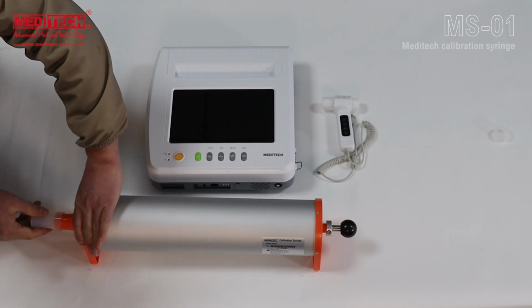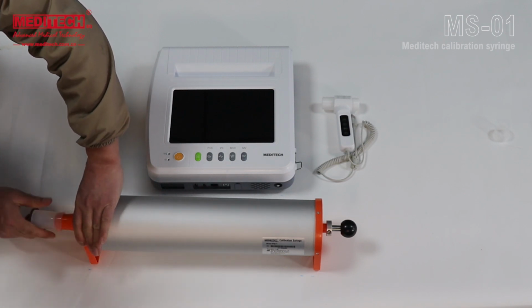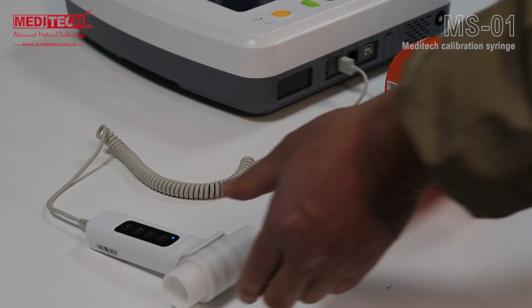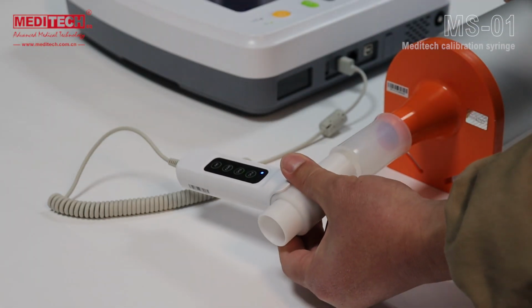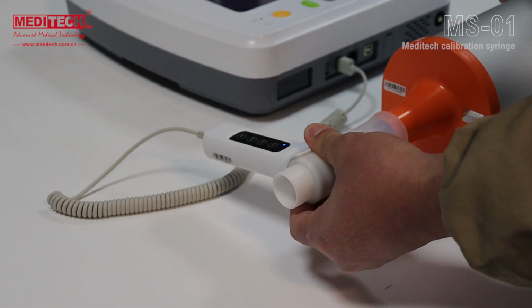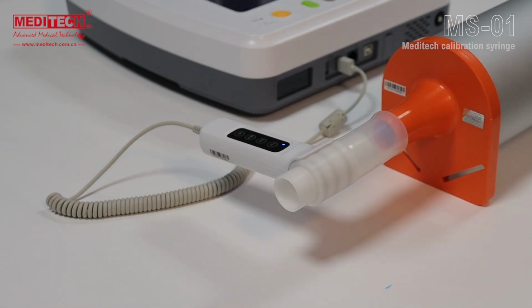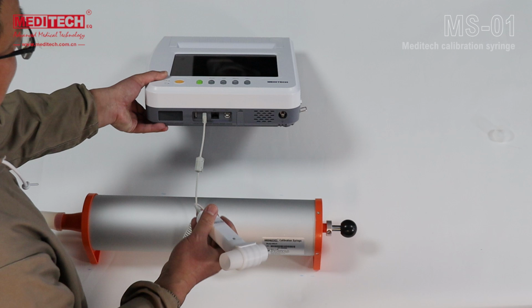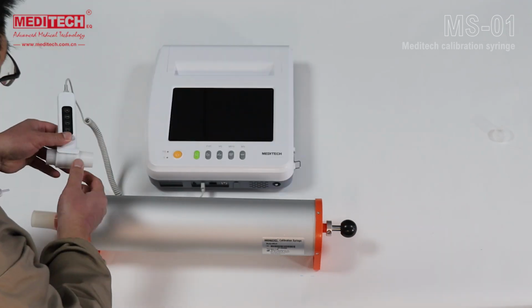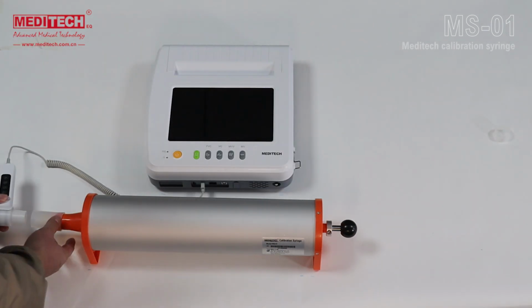Connect the flow gun of the spirometer to the device and the calibration syringe. To do this, use the silicone connector provided and connect the other side to the calibration syringe with a little more force. Check that there are no gaps or air leaks and then connect the flow gun cable to the USB interface. Please select the correct direction as shown and connect it to the silicone connector immediately.